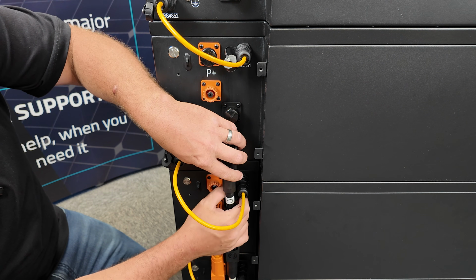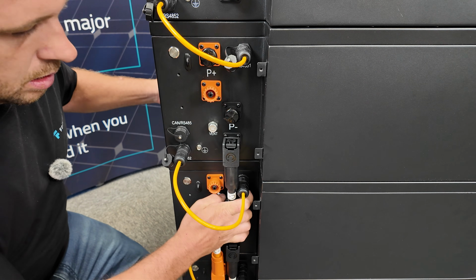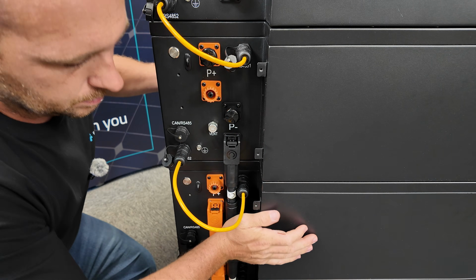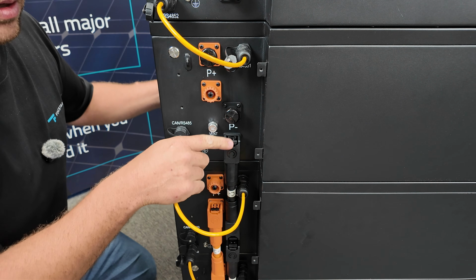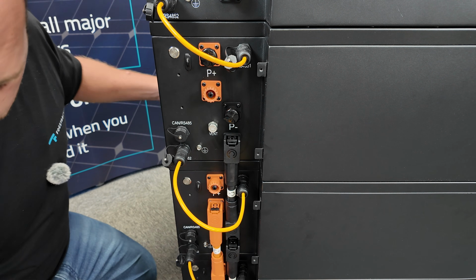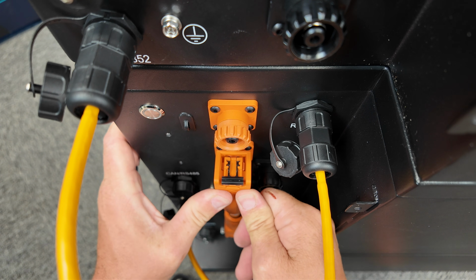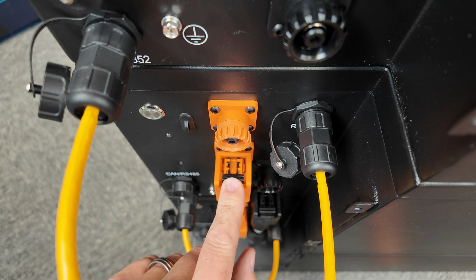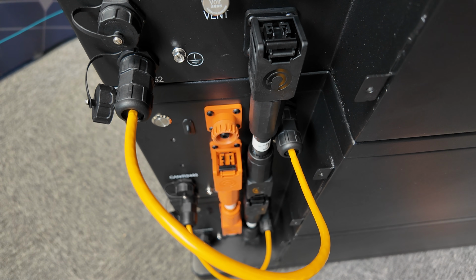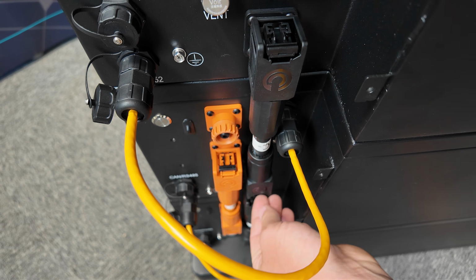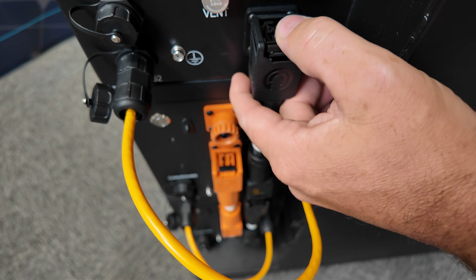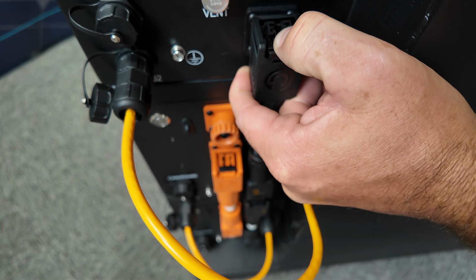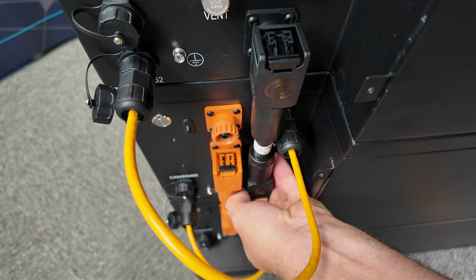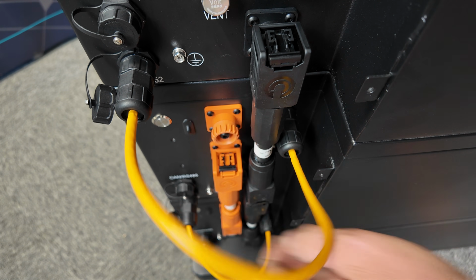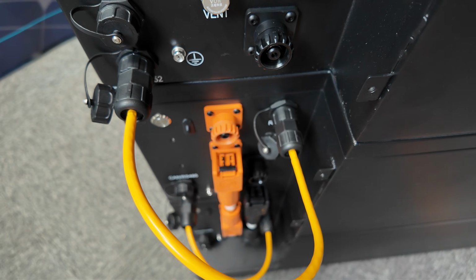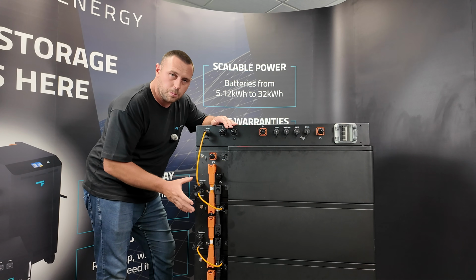On the lower battery you will take the upper port, and on the upper battery you will take the lower port. Push those tabs in to lock in place. Push the wire in, listen for the click, and then push the black tab. If for any reason you need to remove a cable, slide back the black plastic tab on both top and bottom, and then push in here. This pivots like this, and then you can pull back on the connector and remove it. That is the module to module power cables done.